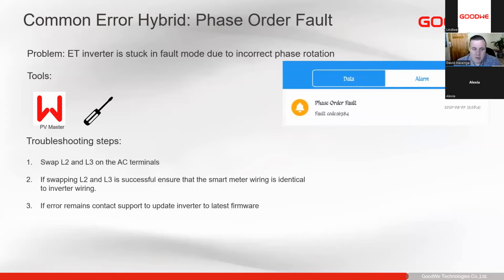So next, very common is phase order fault. As you'll see when you look at alarms, you'll see the fault code 16384. That's phase order fault. Sometimes the utility may change something, go and work on their transformer and restructure it, especially in a country where all the homes are single phase. In Africa, this happens often because it's single phase. All the homes are single phase.